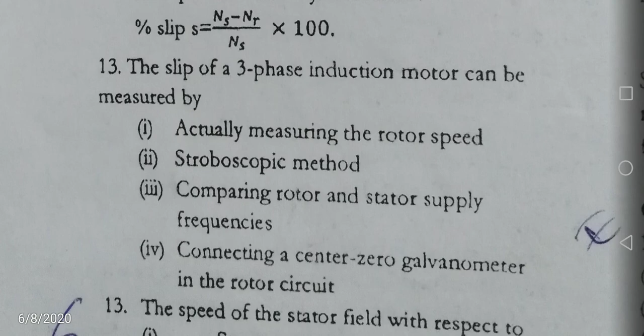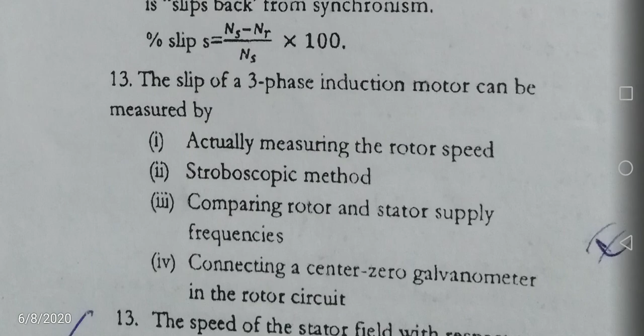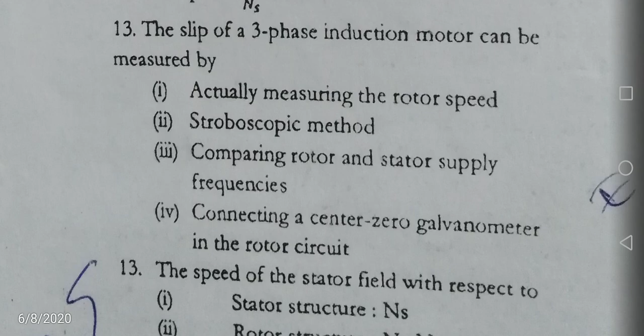The 13th question: the slip of a three-phase induction motor can be measured by actually measuring the rotor speed, the stroboscopic method, comparing the rotor and stator supply frequency, or connecting a center-zero galvanometer in the rotor circuit. All of these are correct. So we get the rotor frequency, and from that the slip equals Fr by F, the rotor frequency by the stator frequency.